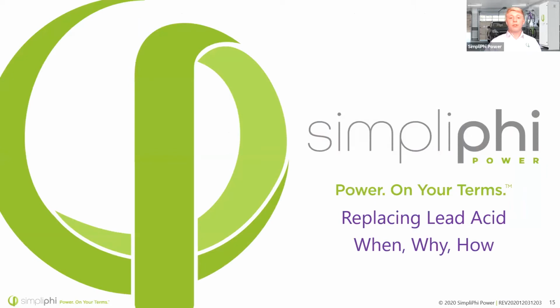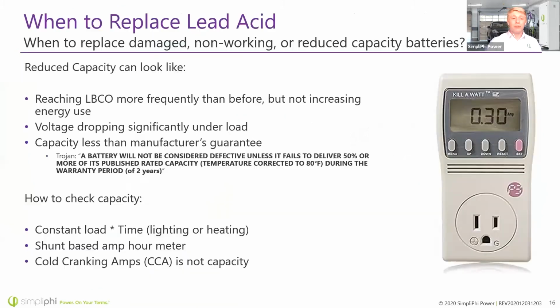So now that we've hopefully troubleshot some of the issues that you could be seeing with your lead-based battery system, let's talk about when you would need to replace your batteries, why, or even how to replace them. So when you want to replace your batteries is if they have severely reduced capacity. Reduced capacity could look like you reaching low battery cutout more frequently than before, but you weren't really increasing your energy usage. It could even look like a voltage dropping under a significant load. So if you turn on your microwave and your battery voltage drops 5-6 volts, that could be an issue right there.